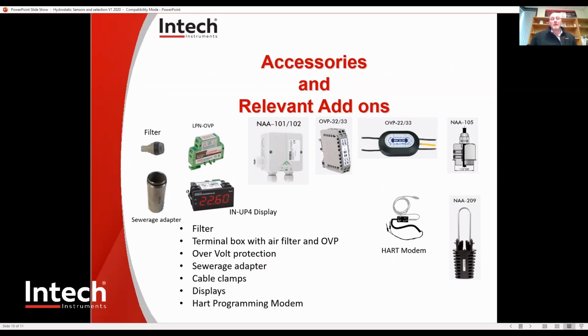We have the hanging clamps. We also have the HART modem for the Nivelco range, so you can reprogram the depth. We have also a different sort of hanging clamp here. I'll show a few of these as well. So this is the sewerage adapter for the Nivelco range.